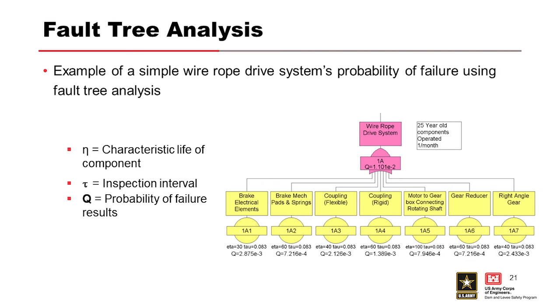So we use those gates, as I mentioned, in fault tree analysis. Here's an example of a simple wire rope drive system's probability failure using fault tree analysis. So the wire rope drive system depends on several components there. The brakes, the brake pads and springs, couplings, motor, gear reducer, a couple of different types of gear reducer there.